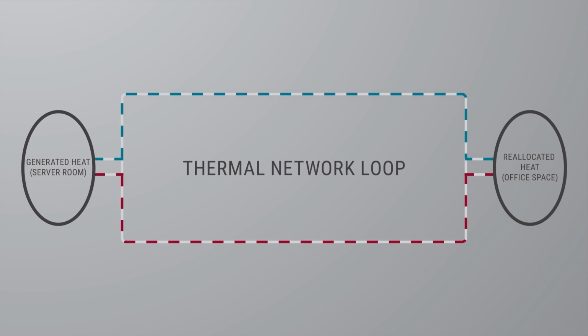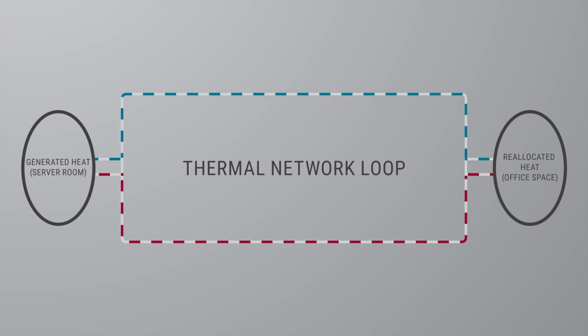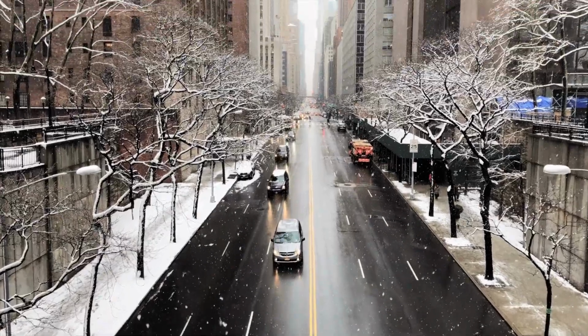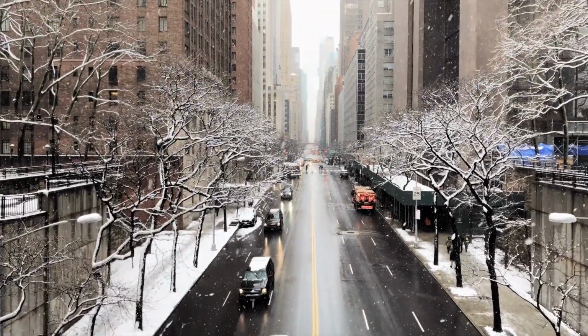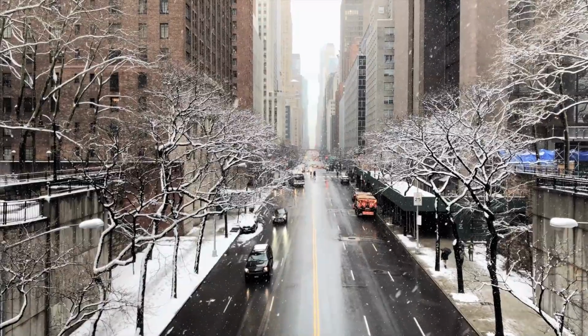We have been including heat recovery chillers into healthcare projects for quite some time. We have a simultaneous heating and cooling load, healthcare is big on that, and it just makes sense. However, almost all of our buildings, in the middle of winter when it's 0 degrees in New York City, are still producing more heat than they need, or at times that we don't need it.